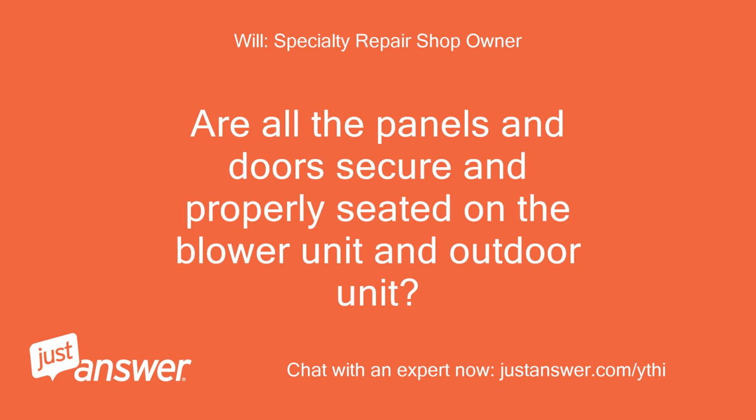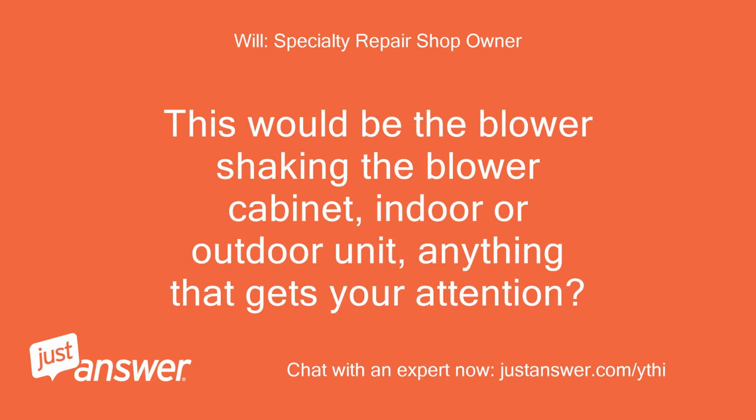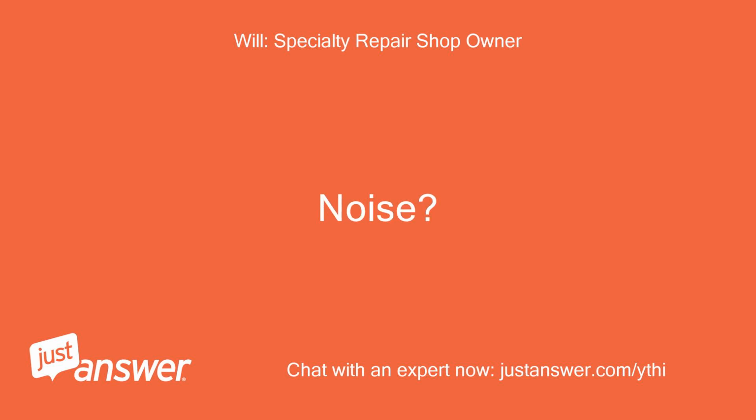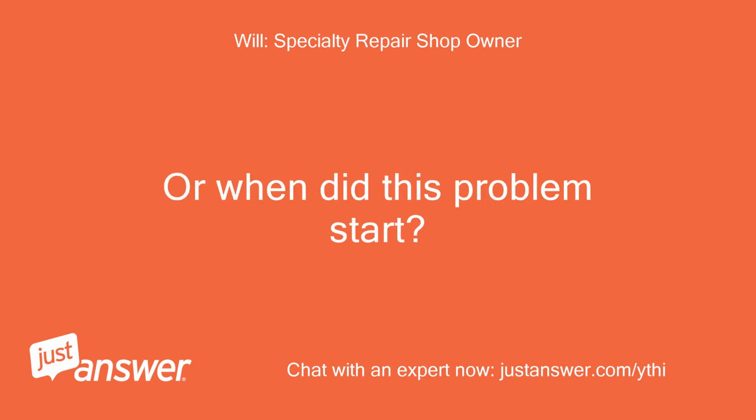Are all the panels and doors secure and properly seated on the blower unit and outdoor unit? Is there any noticeable vibration when the unit comes on in either furnace mode or AC mode? This would be the blower shaking the blower cabinet, indoor or outdoor unit. Anything that gets your attention? Noise? Is this a new problem? Or when did this problem start?